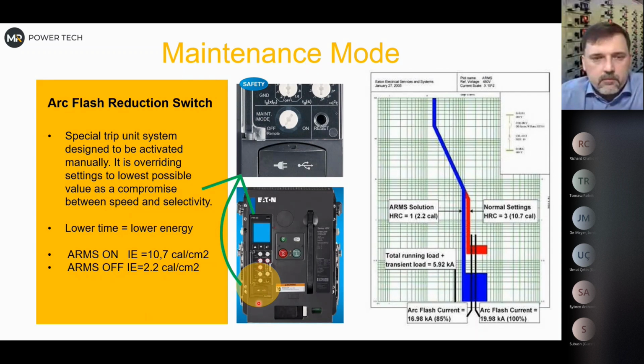The purpose of this is that we bypass the instantaneous settings and short time settings to make the breaker act as fast as possible. Because we are doing some maintenance work, and instead of having, like here, 12 or 10 calories, we would like to have 2.2. So it means that we are better protected, we have less energy. We might use different PPE, depending on what kind of change it is, because it might drop from 40 calories to 20 also.